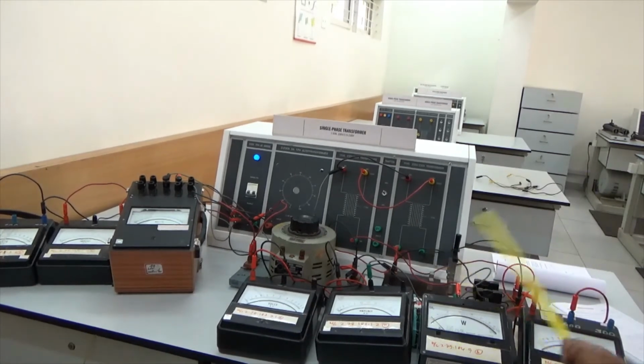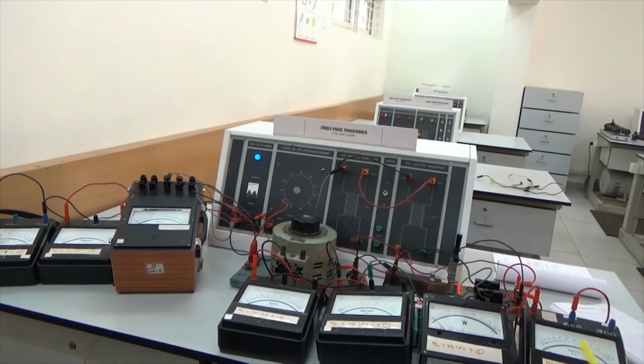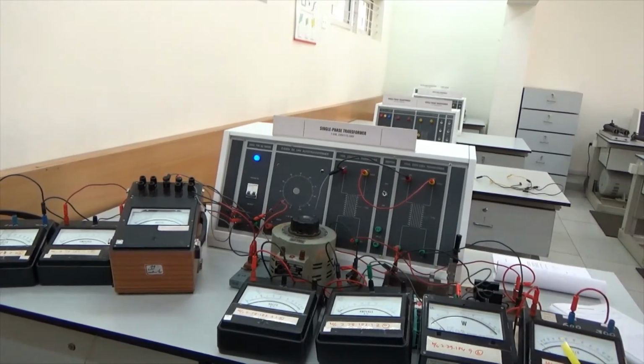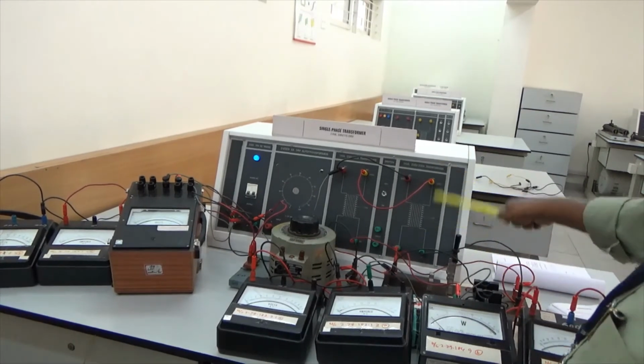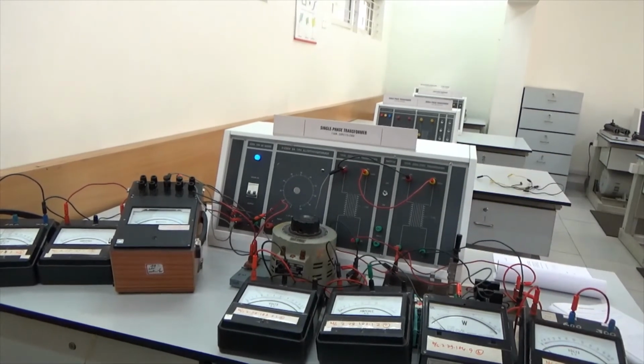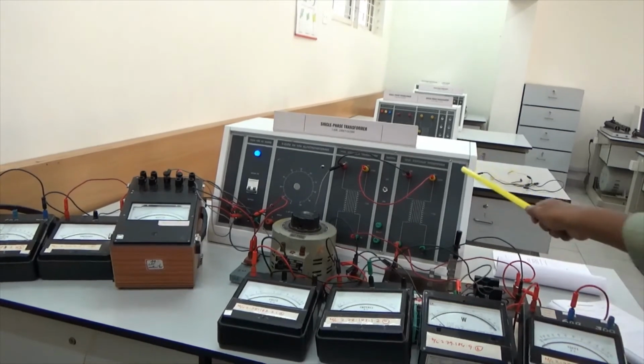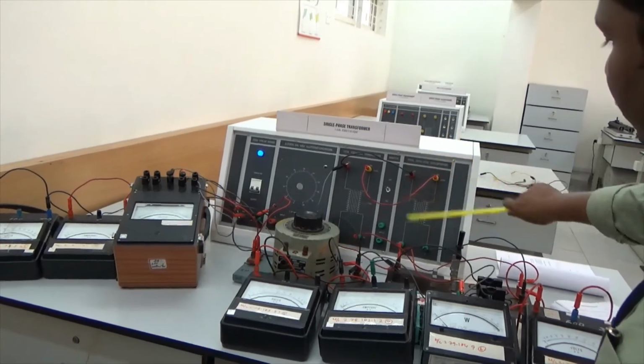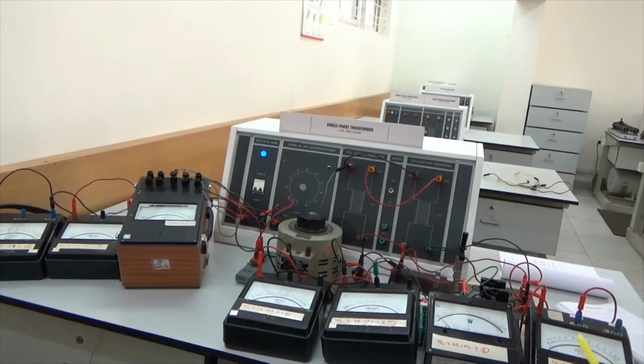Otherwise, if at any moment when the supply is closed it shows double the voltage, 230 plus 230, 460, then it means that the two voltages are out of phase. In that case you have to switch off the set, interchange the terminals, and make the voltage 0.